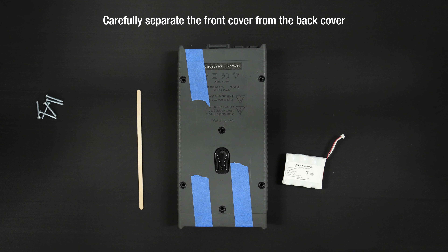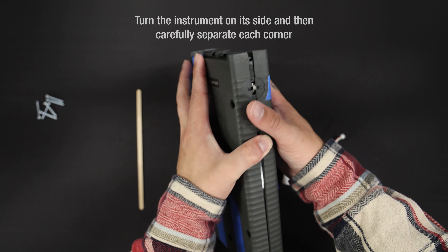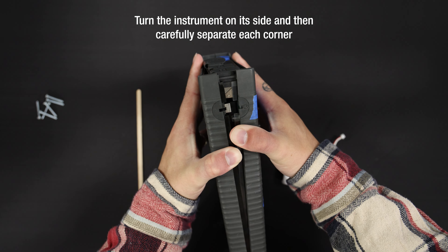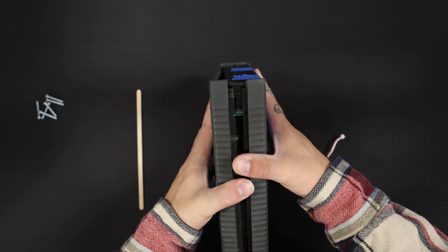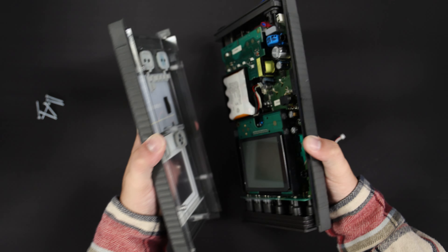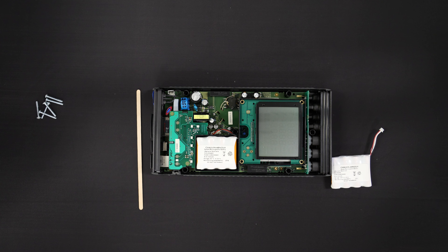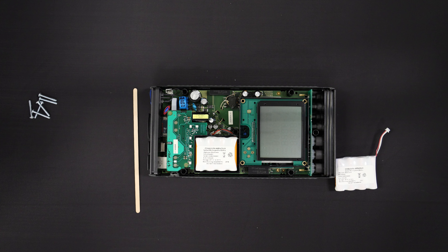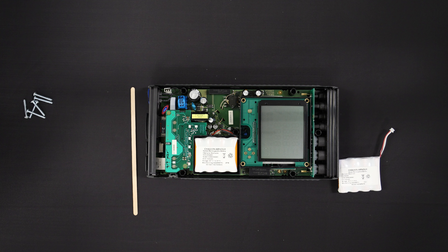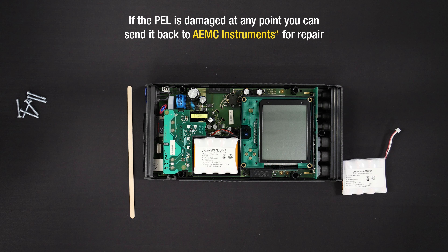Carefully separate the front cover of the PEL from the back cover. The two covers fit together tightly, so it may be difficult at first to separate them. One way to make this easier is to turn the instrument on its side and then carefully separate each corner, starting with the bottom right corner. Pull the covers apart, ensuring that the top and bottom end plates remain attached to the back cover. Do not allow either end plate to become separated from the back cover, because this may damage the PEL input and connection terminals.